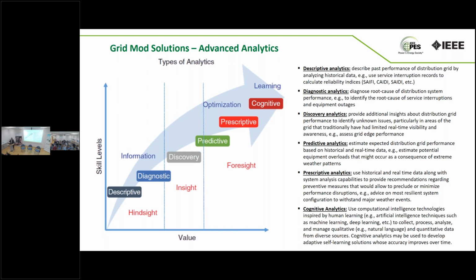And the patterns occur not only when the fault happens, but more importantly before it occurs—for example, a tree touching a line produces a different type of pattern. So utilities are collecting data from advanced sensors and fault circuit indicators with that capability, and starting to analyze those patterns to identify precursors of a fault.